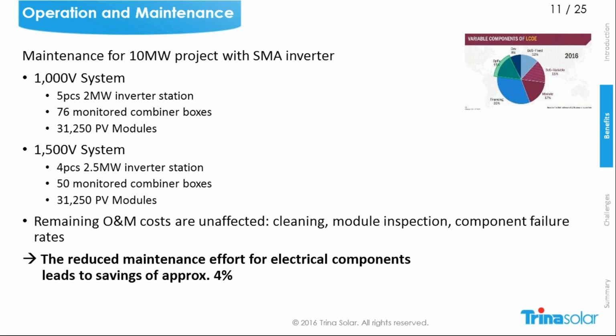The same applies to the combiner boxes. Due to the longer strings, the number of combiner boxes is reduced from 76 down to 50. For sure, the number of modules is the same, 31,250, because they have the same power rating. That means we have fewer components to check in a 1500 volt system, and this means a reduced effort for frequent inspections, like module inspections, inverter cleaning, and also cleaning or inspection of the combiner box. The module inspection and cleaning will be the same, but the reduction of the components you have to check on the inverter side and combiner box will lead to an OPEX saving of approximately 4% compared to a 1000 volt system. So the higher voltage also enables savings on the operation and maintenance side.